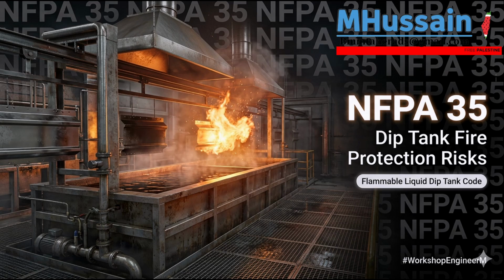Okay. You then pump clean, uncontaminated outside air into that room so that the atmospheric pressure inside the room is physically higher than the pressure out on the factory floor. Because the pressure inside is pushing outward. Exactly. The heavy explosive vapors on the floor simply cannot penetrate the room against that pressure gradient. Every time a worker opens the door, the clean air forcefully rushes out, physically pushing the hazard away. That's just so elegant.